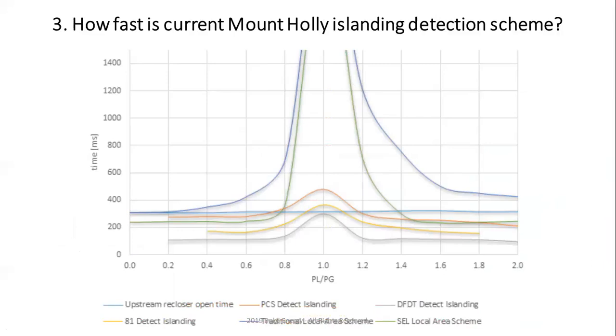So somebody asked, how fast is this scheme, right? And somebody asked about non-detection zones, right? Well, here's what I can tell you. The blue line and the green line that you see over there are for PL over PG equals 1.0, which means that the loading is equal to the generation. They are based on the 27, 59, and 81 settings. This is from a book and from a paper that was written. If you search, it's an SEL book that was published probably last year, and they have these curves over there, right? If you see our scheme that I showed you, you can see 3 lines, actually 4 lines, but 3 lines that show the response. The red line that you can see is the line that shows the detection time for the island, on the left side, if it was detected by the battery inverter PLC.